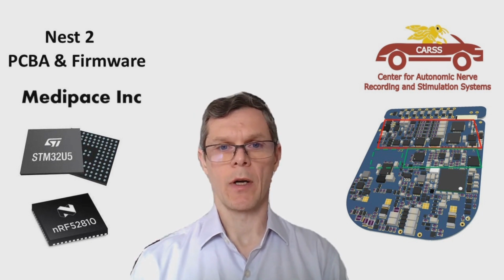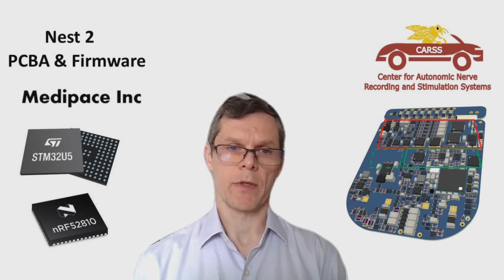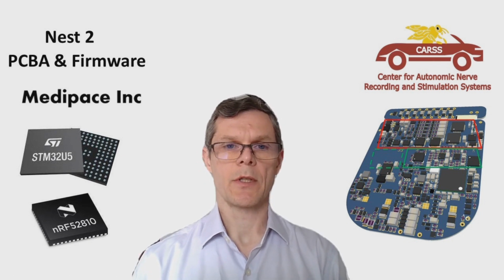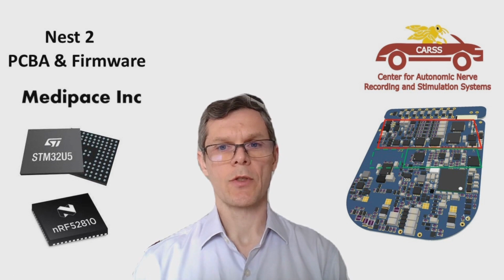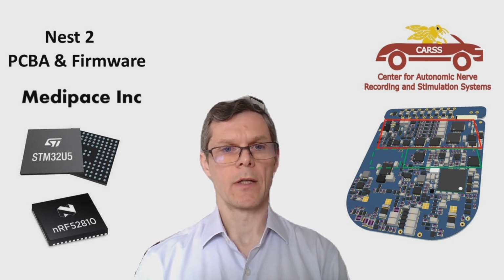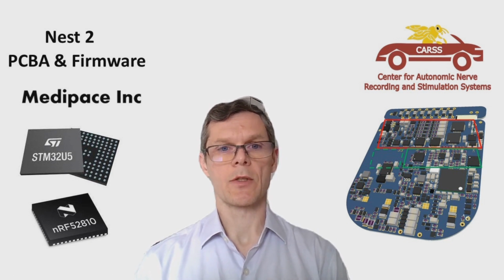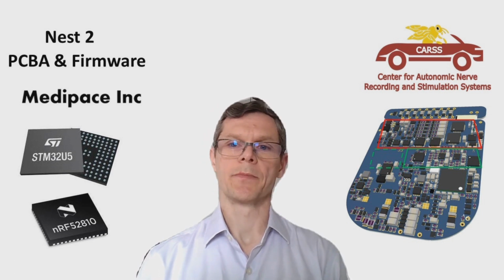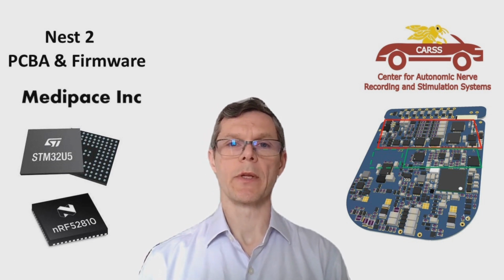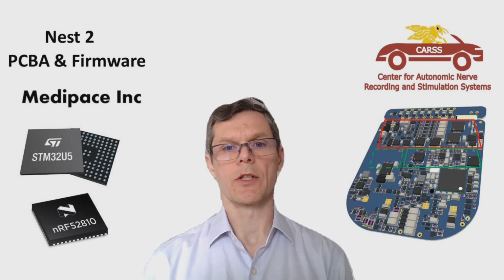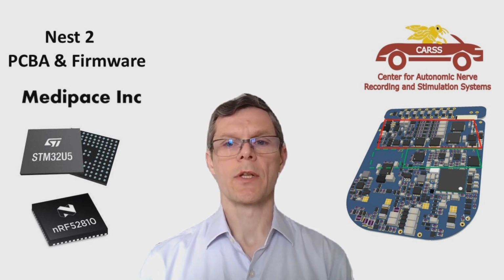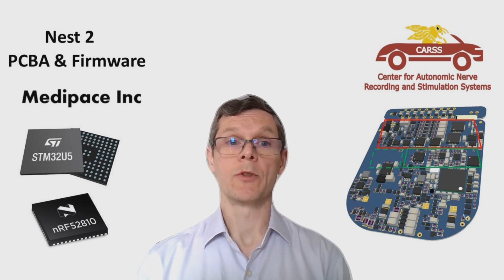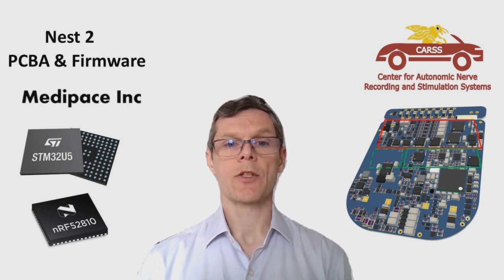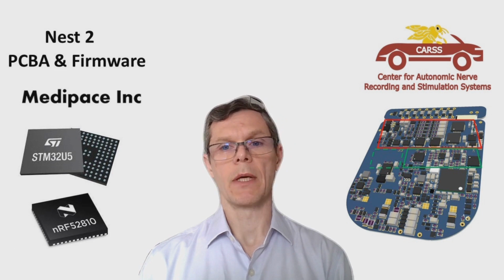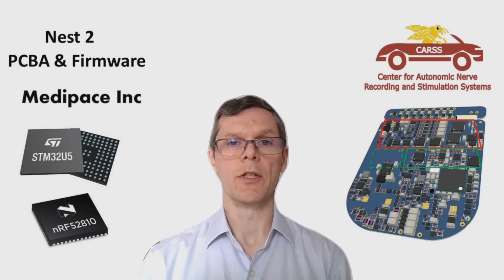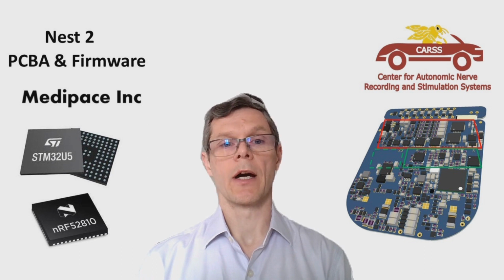Another concept we are incorporating is modularity. As you can see on the right, the stimulation circuits are in the red area, and multiple sensing circuits are in separate green areas. Depending on the stimulation target and disease indication, the stimulation channels can be adjusted from 1 to 8, and the sensing channels can be selected based on the use of EKG, EMG, temperature, and other sensing leads.